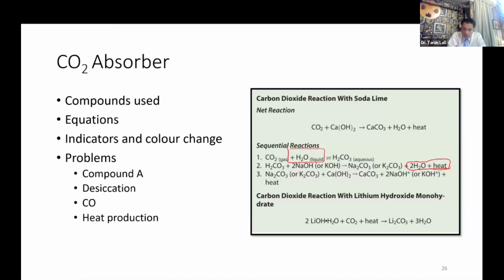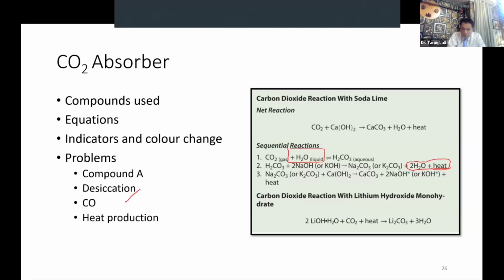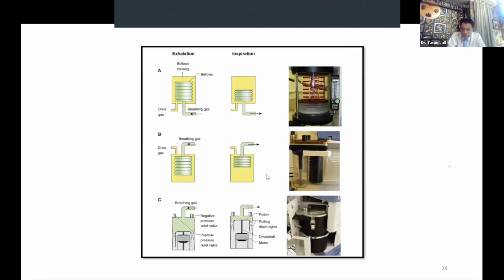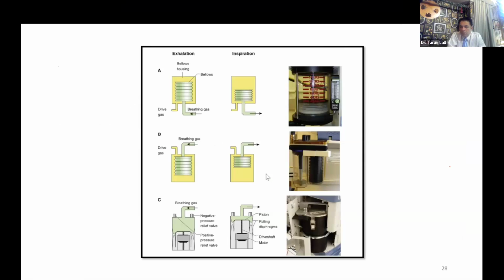But again, as you see, if we have used the absorber for some time, it produces water, and therefore that desiccation thing is taken care of after some time. But that first case on Monday morning is when you can get this problem of carbon monoxide production. Heat I have already covered, a problem with Baralyme. Then the other thing you saw in the circle system is your ventilator. In this figure, we will just touch on three common designs of ventilators: the ascending bellows, descending bellows, and the piston.